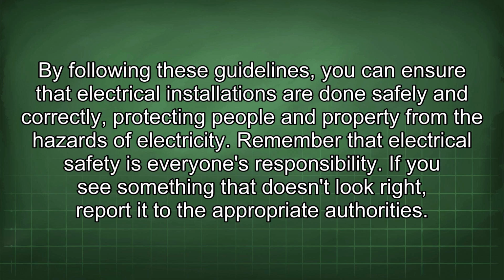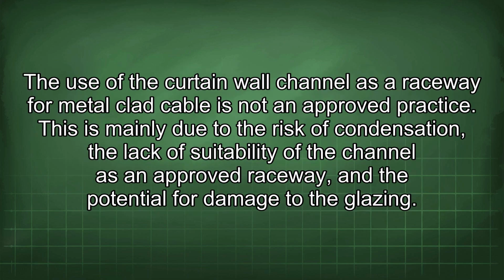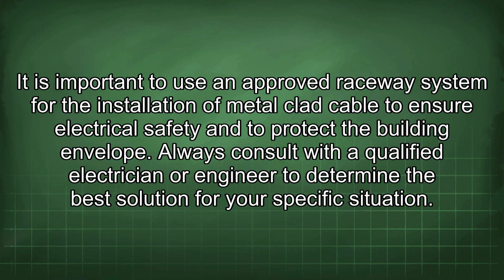By following these guidelines, you can ensure that electrical installations are done safely and correctly, protecting people and property from the hazards of electricity. Remember that electrical safety is everyone's responsibility. If you see something that doesn't look right, report it to the appropriate authorities. The use of the curtain wall channel as a raceway for metal-clad cable is not an approved practice. This is mainly due to the risk of condensation, the lack of suitability of the channel as an approved raceway, and the potential for damage to the glazing. It is important to use an approved raceway system for the installation of metal-clad cable to ensure electrical safety and to protect the building envelope.